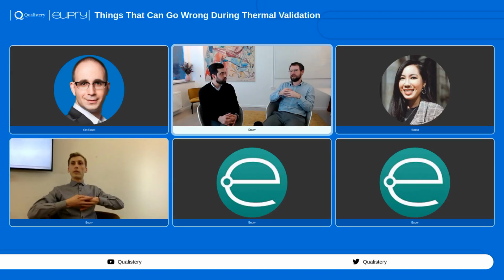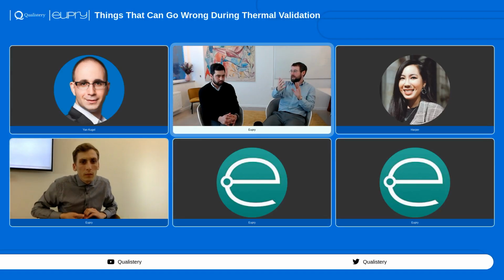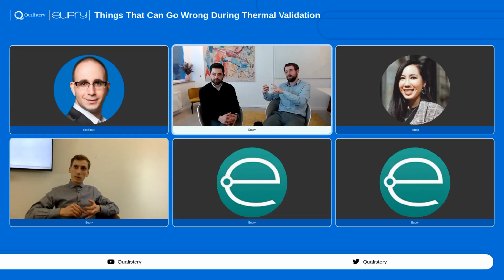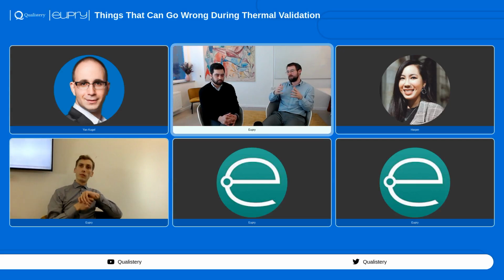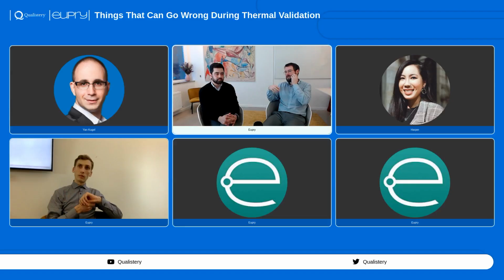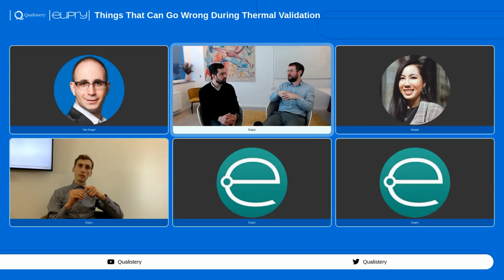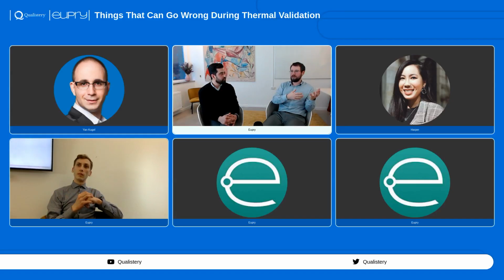Another approach we've seen a few times is to take a sample, start-calibrate all your sensors, and then take out a sample of the data loggers used and end-calibrate them. Because if they all experience the same environment, the chances of them all drifting in the same manner is quite reasonable. But then you also have specific scenarios where if you drop a temperature sensor, some types will shift in temperature.